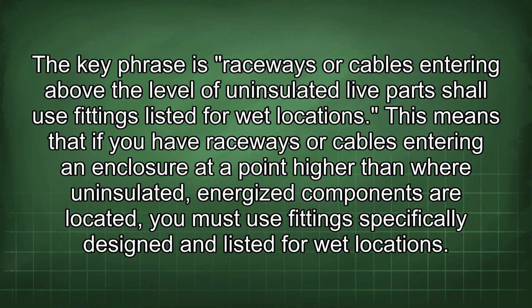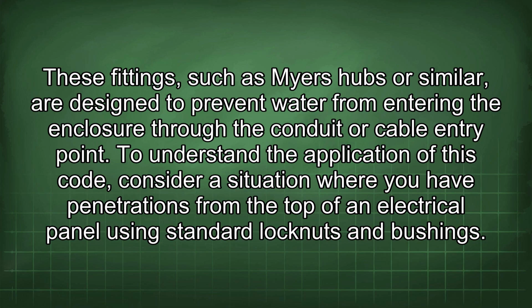The key phrase is raceways or cables entering above the level of uninsulated live parts shall use fittings listed for wet locations. This means that if you have raceways or cables entering an enclosure at a point higher than where uninsulated, energized components are located, you must use fittings specifically designed and listed for wet locations. These fittings, such as Myers hubs or similar, are designed to prevent water from entering the enclosure through the conduit or cable entry point.